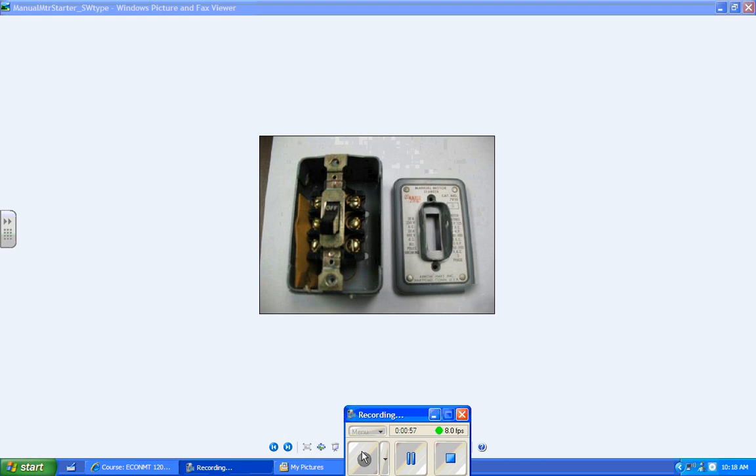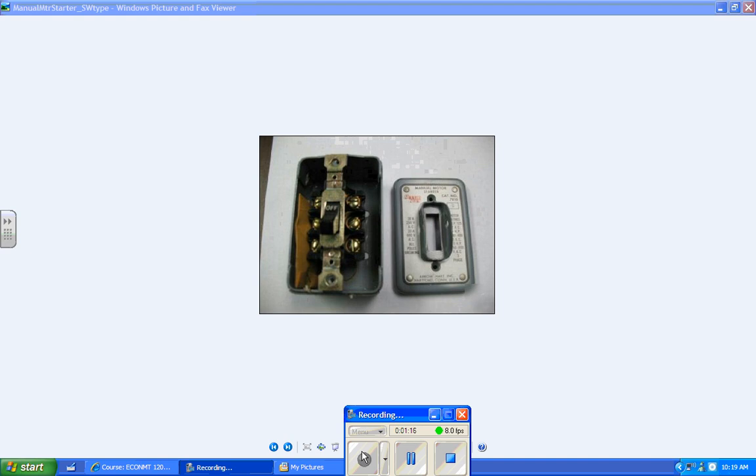Usually it's specific to the motor that it came with. A lot of times a package air conditioner will come with a manual motor starter, and you can operate it from a light switch type device. This is a package air conditioning manual motor starter. The only difference between that and a very heavy duty light switch is that it has overload protection built into it.